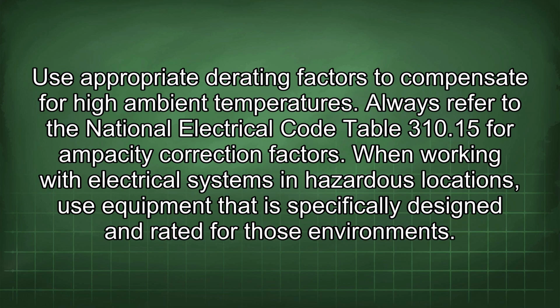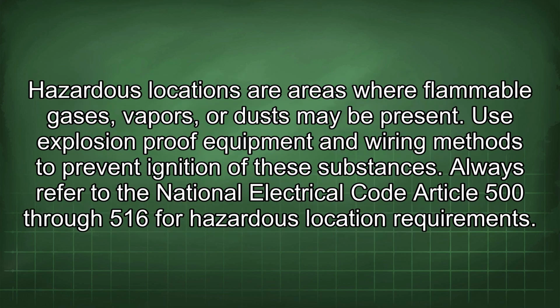When working with electrical systems in hazardous locations, use equipment that is specifically designed and rated for those environments. Hazardous locations are areas where flammable gases, vapors, or dust may be present. Use explosion-proof equipment and wiring methods to prevent ignition of these substances. Always refer to the National Electrical Code Article 500 through 516 for hazardous location requirements.